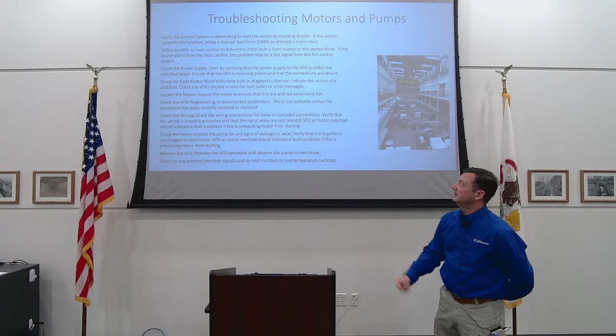The first step from my perspective is, when a motor does not start, you normally notice it because the SCADA system or the control system should be calling for the pump to run, and the pump's not running. So the first thing to do is take the whole system and cut it in half. Is it the SCADA system or is it something out at the motor itself? So on the SCADA system, verify: is the SCADA system calling for the pump to run? Okay, looks like it's calling for the pump to run, but for whatever reason, it's not running.